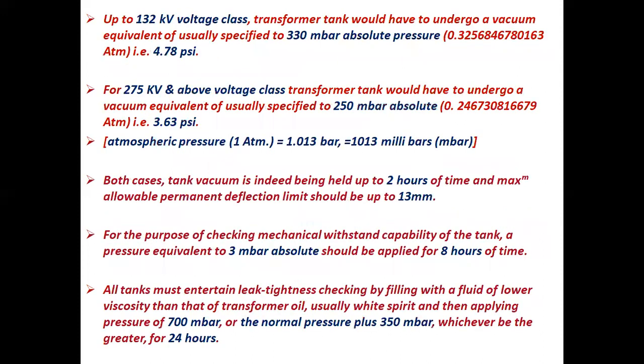Up to 132 kV voltage class, the transformer tank would have to undergo a vacuum equivalent of usually specified 330 mbar absolute pressure, that is 0.325684578016 atm, that is 4.78 psi. For 275 kV and above voltage class, the transformer tank would have to undergo a vacuum equivalent of usually specified 250 mbar absolute, that is 3.63 psi. Atmospheric pressure equals 1.013 bar, equal to 1013 millibars, mbar.